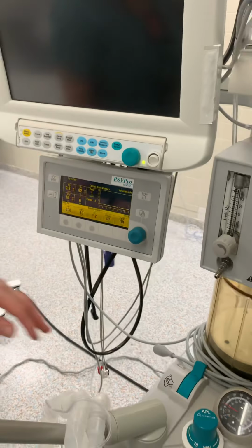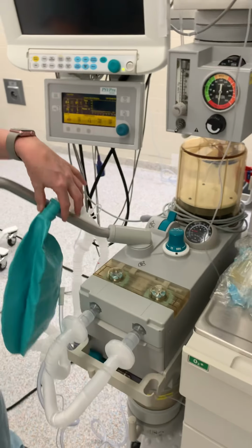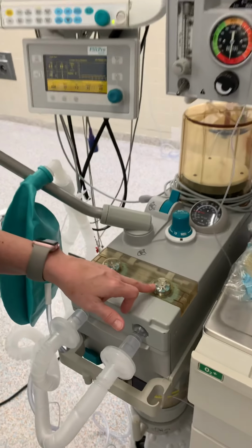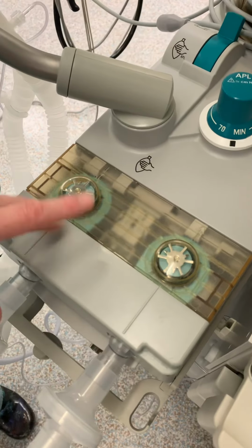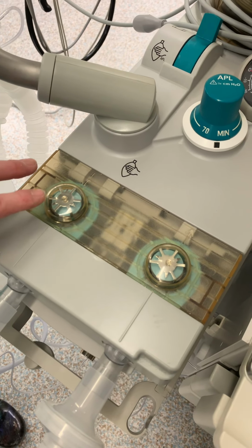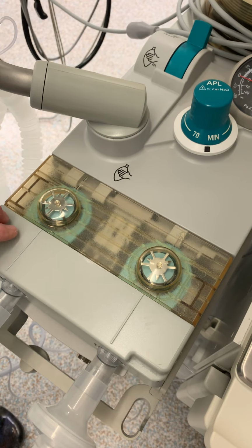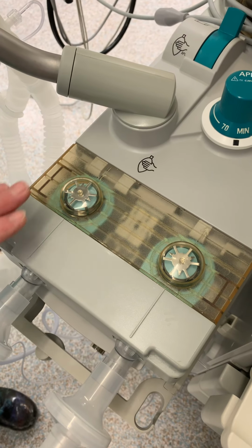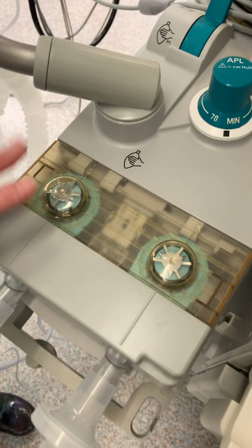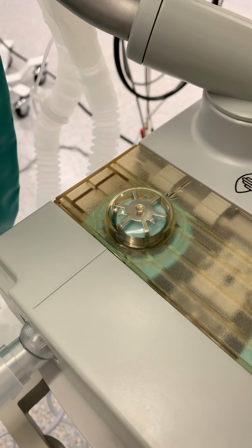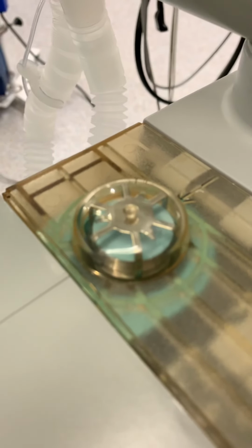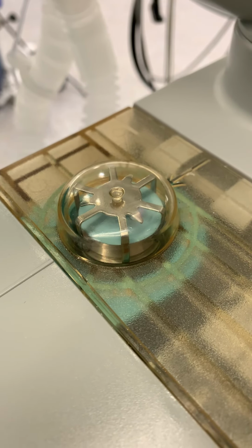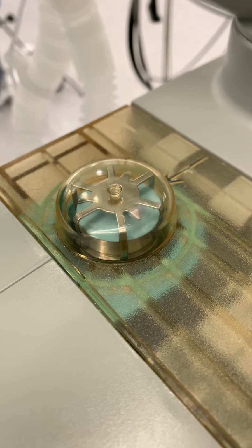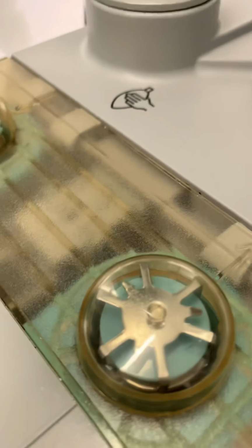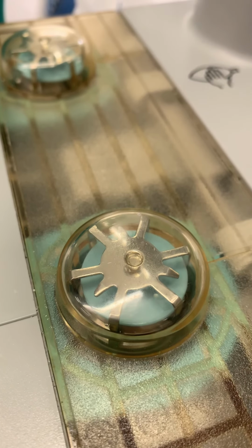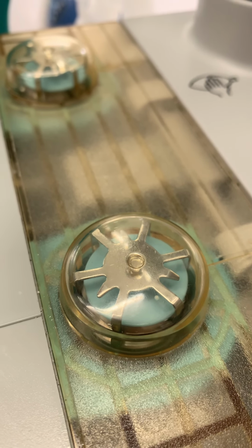And as that's building, this machine is good to use because you can see your inspiratory and your expiratory flow valves. You want to see them fluttering. Fluttering means that they're not sticking, which would be an obstruction to ventilating a patient. So they should be free and fluttery when air is passing through them. And I don't know if we can show you that well enough, but again, sometimes this can take a minute.